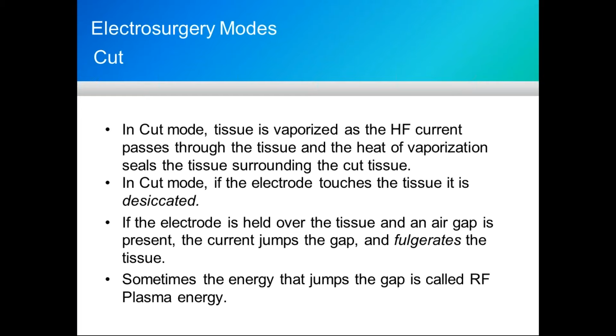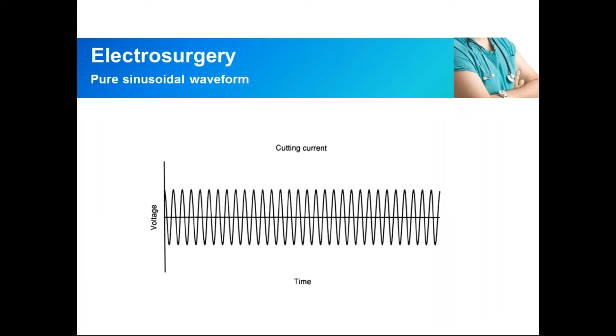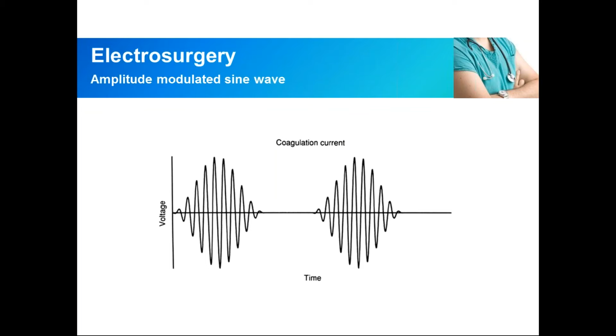In coag, it's basically the same operation as in the cut mode. This is the waveform of the cut, and you can see it is voltage over time. This is the coagulation waveform. You can see it's voltage over time also, but you can see the difference in the two waveforms. Let me back up for a second so you can take a look at the other one. And that was cut, and this is coag.